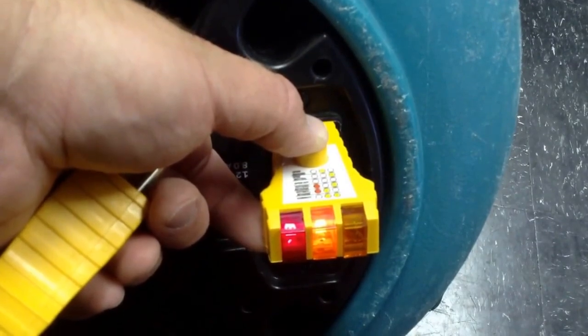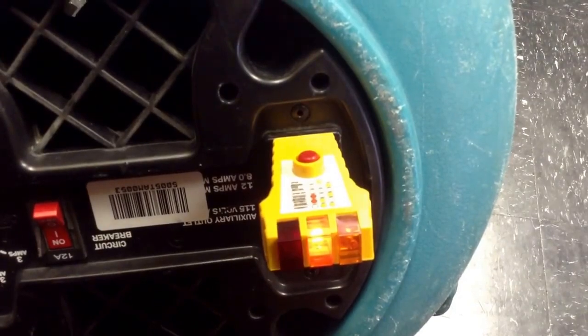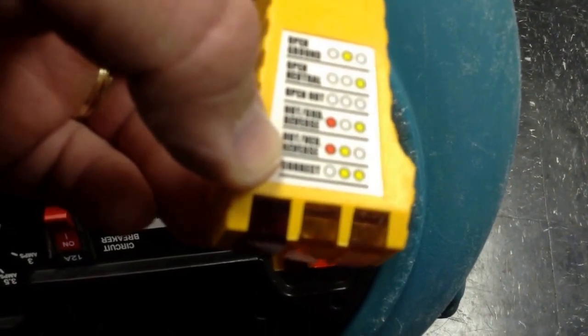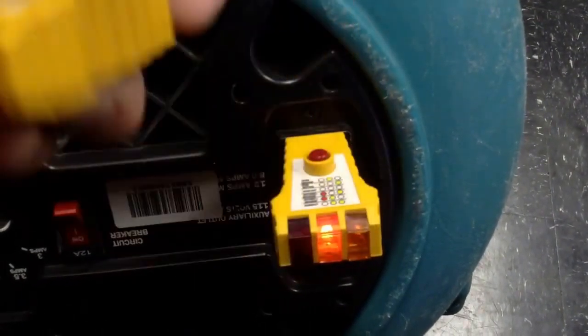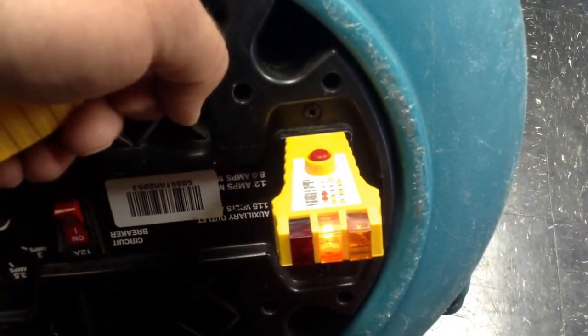So we have the red light on the left and the yellow light in the middle. It means when it's trying to trip, our hot and neutral are reversed, the second to bottom scenario. So this outlet on this piece of equipment is wired incorrectly.